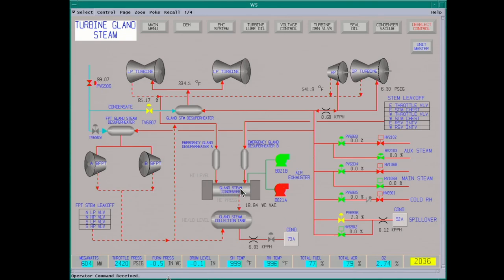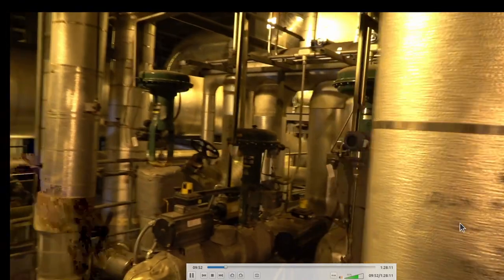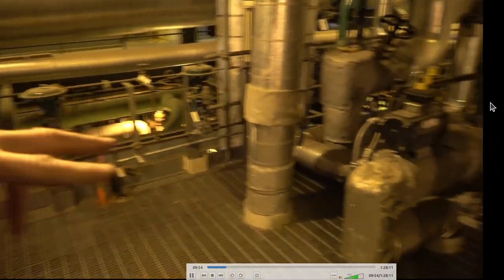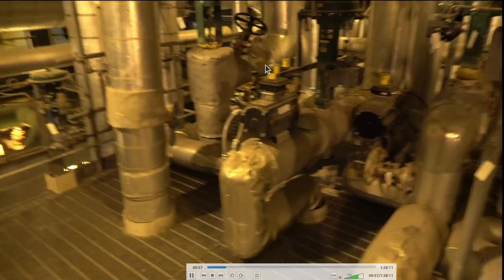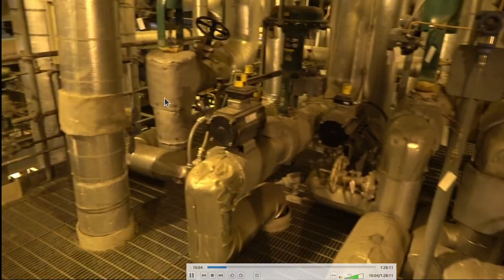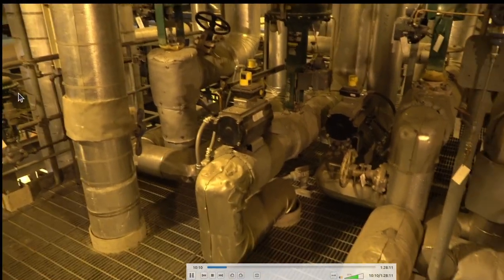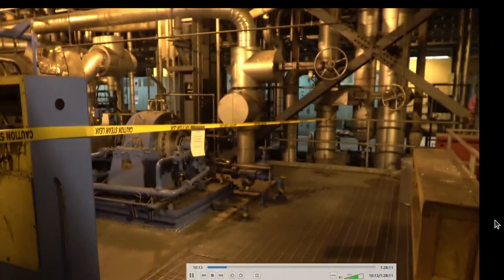Here's your gland steam exhaustor and the pump on it — it pulls part of the excess steam/air mixture out of the turbine to keep any air from in-leaking. This is the gland steam valves area — the drawing makes a lot more sense than looking at the actual piping. Spill-over is here and you have your aux steam here. Back here are the sprays for your feed pump sealing steam — you have to cool the steam down before it goes into the steam seals.